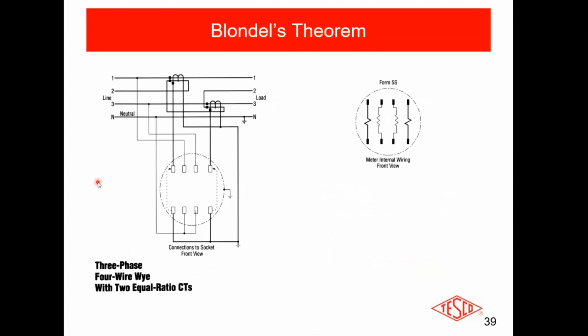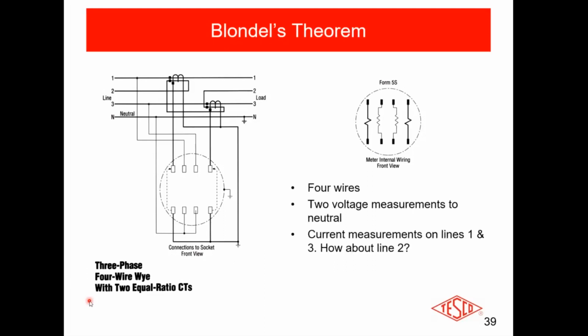Now I'm going to take a 5S meter. Same 5S meter. I'm going to set up a 5S socket. And this time I've got a 3-phase, 4-wire Y with 2 equal ratio CTs on here. All right, and I'm going to try and meter it. This is a setup that you may see on your service territory. It's possible. It's not all that uncommon. All right. I got 4 wires. I got 2 voltage measurements to neutral. I got current measurements on 1 and 3, but not on 2. This does not satisfy Blondel's theorem, which means it will sometimes give me accurate measurements, and sometimes it's not. It's not necessarily going to be far off, but I'm going to lose a few percent in my accuracy.